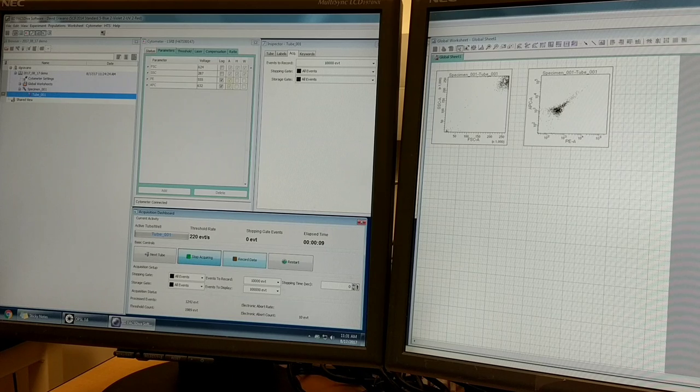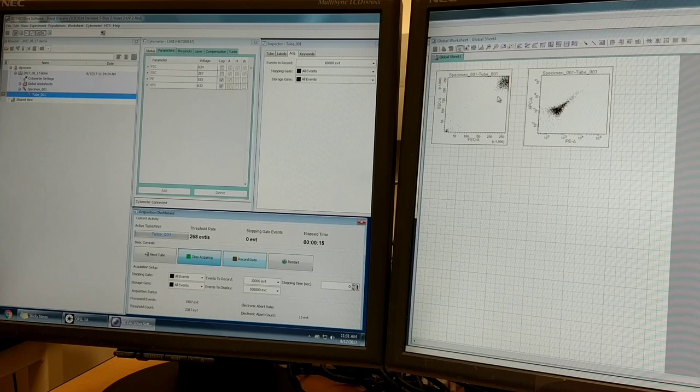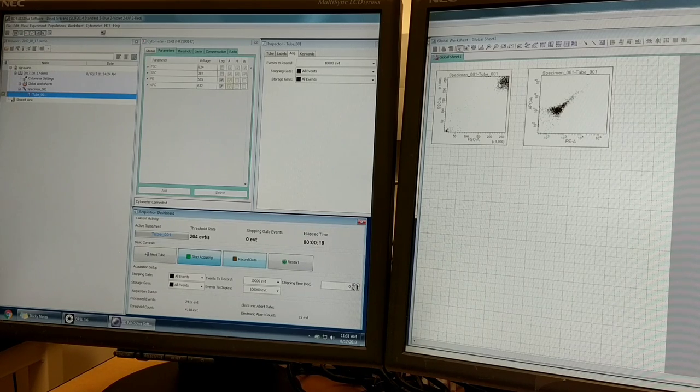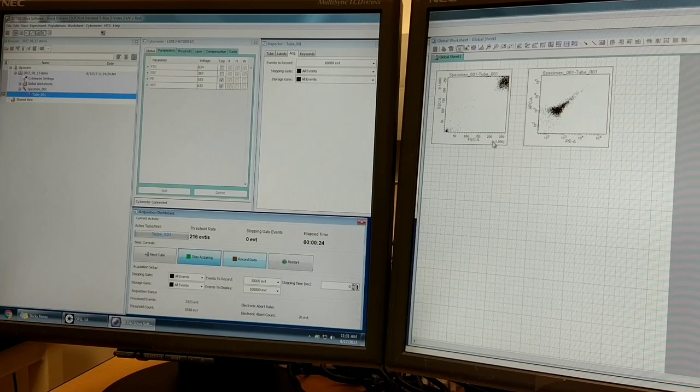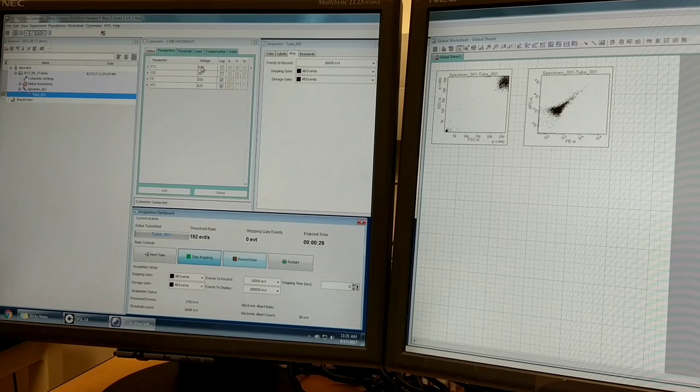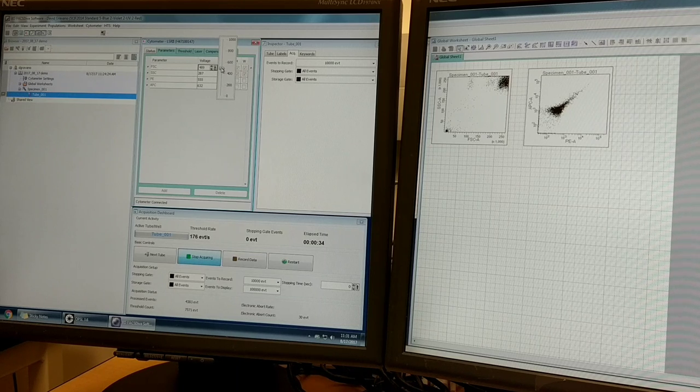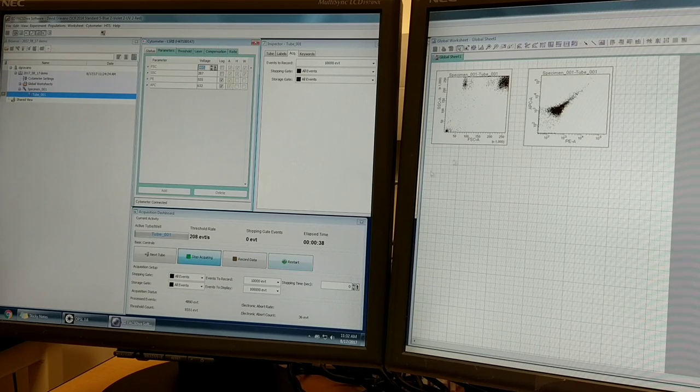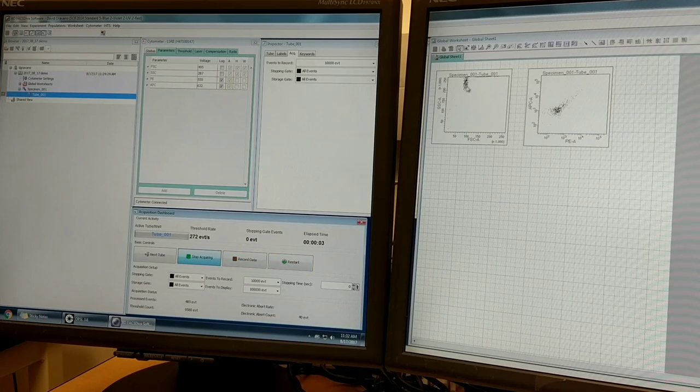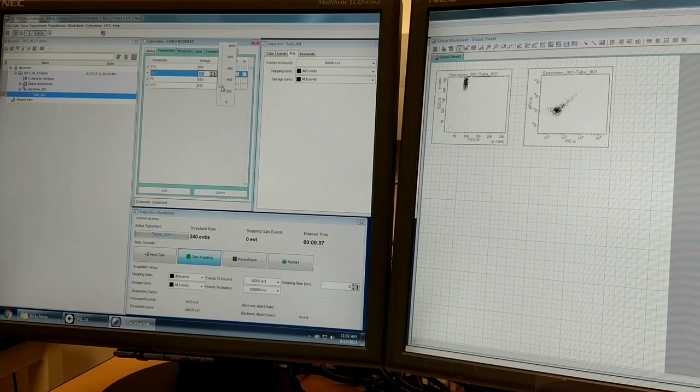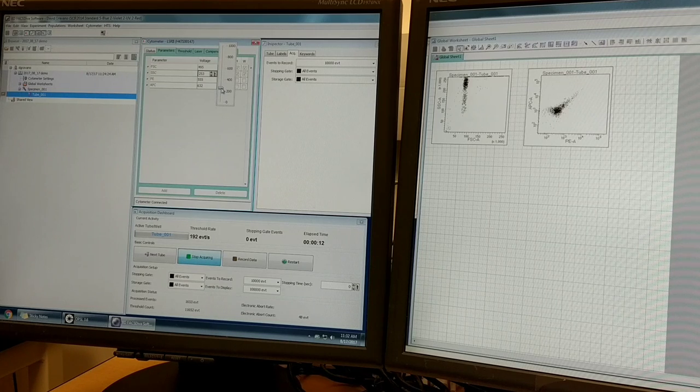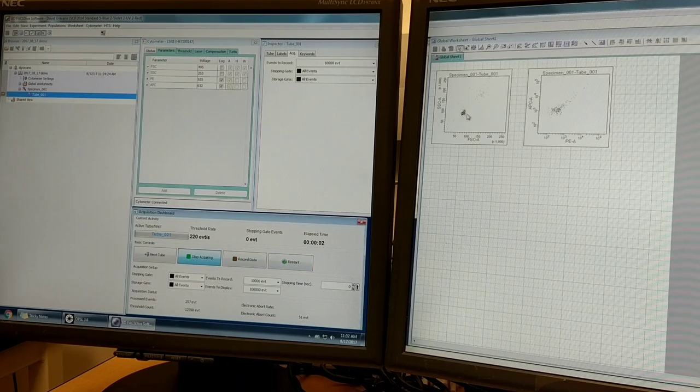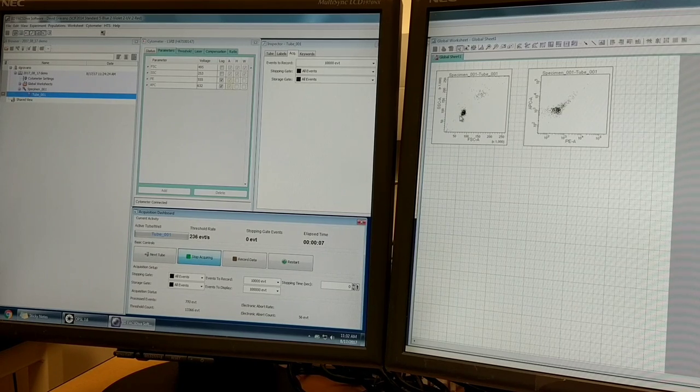As the dots come up, you can see there's some stuff in the bottom left and some stuff in the top right. From prior experience, I can tell the beads are going to be up here in this top corner. So I know my forward scatter detector is set too high, and my side scatter detector is also set too high. I'm going to drag down the forward scatter, and the population will move. You have to hit the restart button to refresh the data on the screen. Now I still need to bring it down on the side scatter, so I'm going to grab that slider and bring it down to where I have my beads approximately where I want them. Most people want their beads or cells of interest toward the middle of the screen.